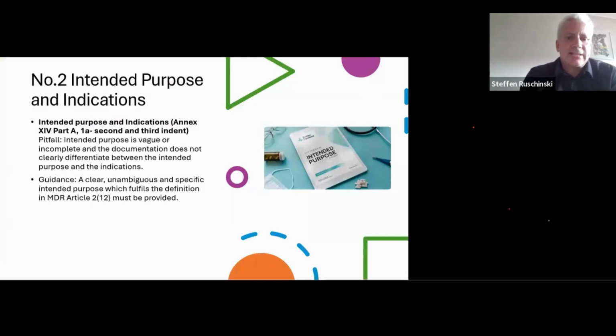So the second pitfall is that the intended purpose is vague or incomplete, and the documentation does not clearly differentiate between the intended purpose and the indications. We need a clear, unambiguous, and specific intended purpose, which fulfills Article 2(12) of MDR. Intended purpose is critical for determining that the device is a medical device, and further the device's risk classification and clinical data requirements. It is subject to scrutiny by the notified body and will be challenged if vague or incomplete.